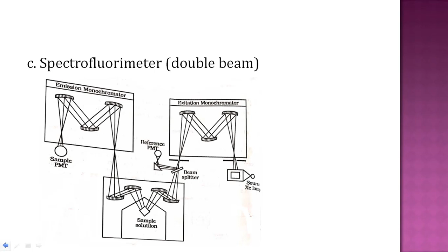Here you can see one monochromator is the excitation and the second is the emission monochromator. Meaning, from the radiation source, the excitation monochromator gives the radiation necessary to be absorbed by the sample, and the emitted radiation coming from the sample goes to the emission monochromator and finally to the PMT, meaning the detector.